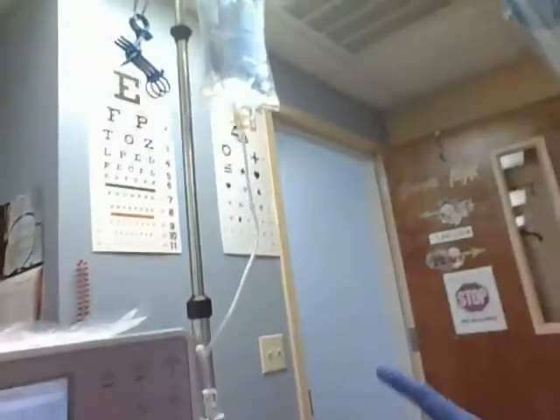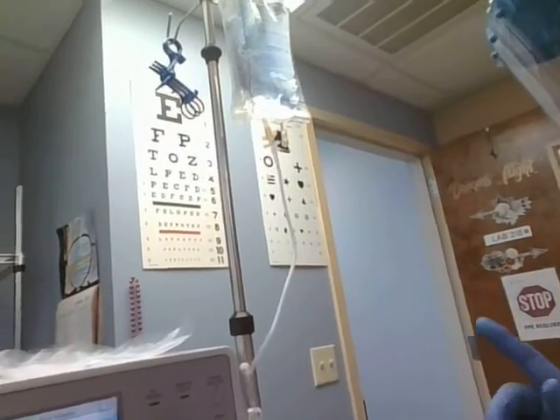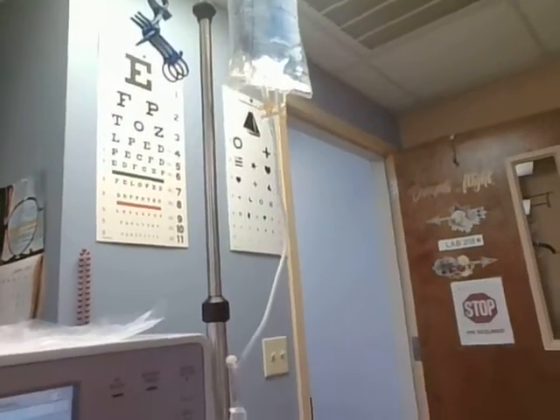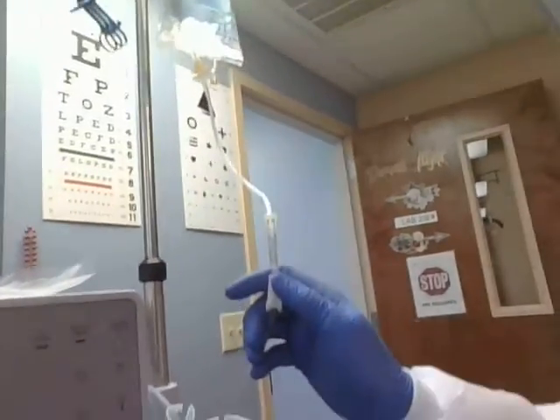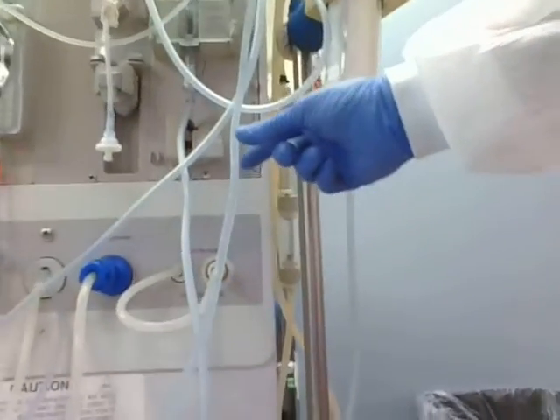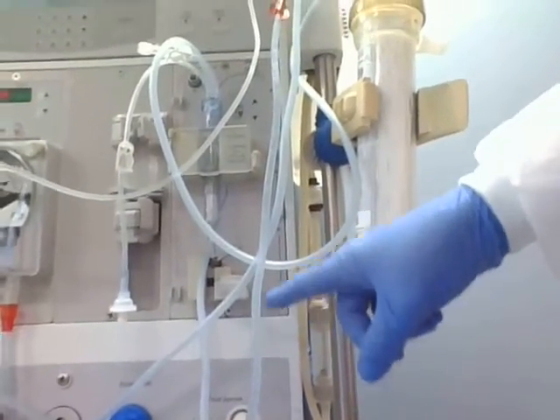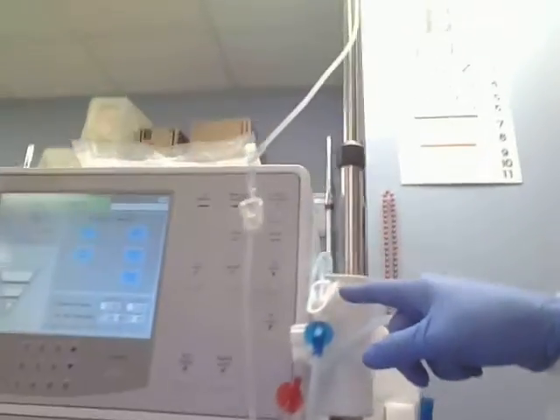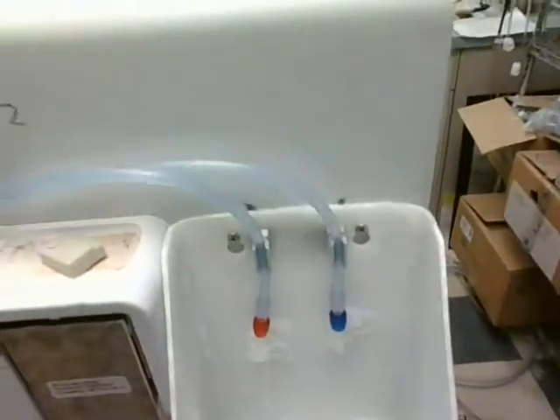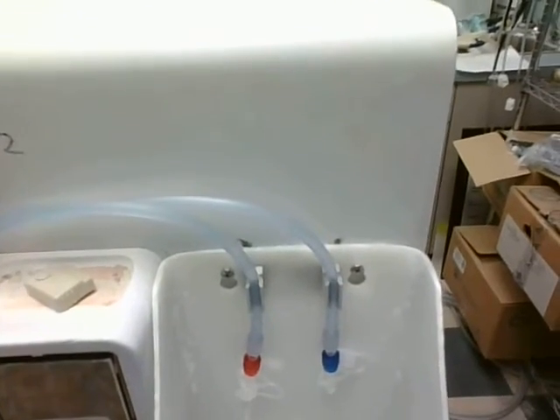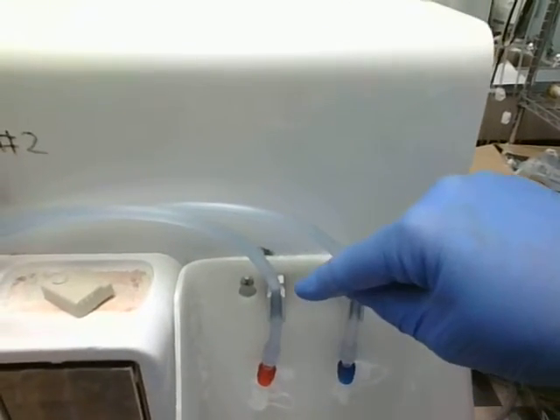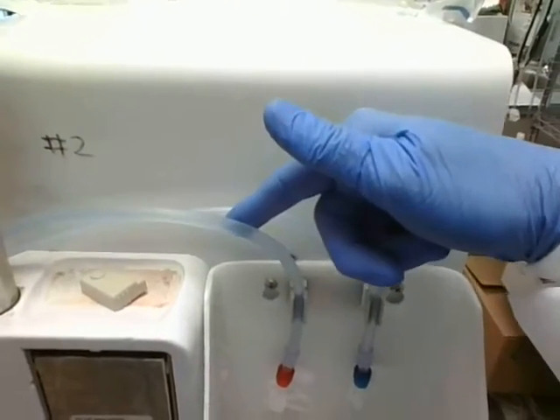Now, the reason that I clamped this line is because I wanted to show you how the priming process works. So right now I'm going to unclamp this saline, and I want you to follow the saline as it comes through. If you can see the saline coming through this line here, you see those bubbles coming through? That's my arterial line. It is a free-flowing line of saline, and it's going to come out into my saline bucket. And I'm going to let that run until I get no more air bubbles coming through there.